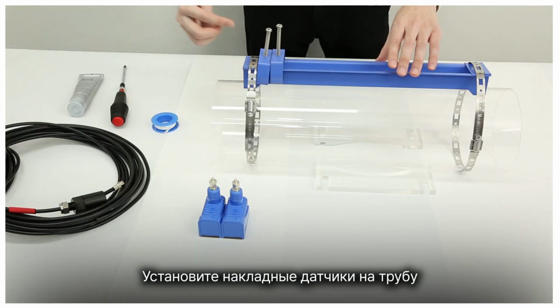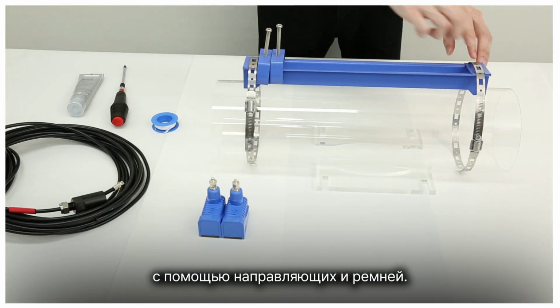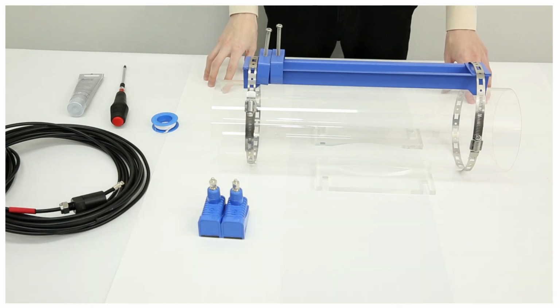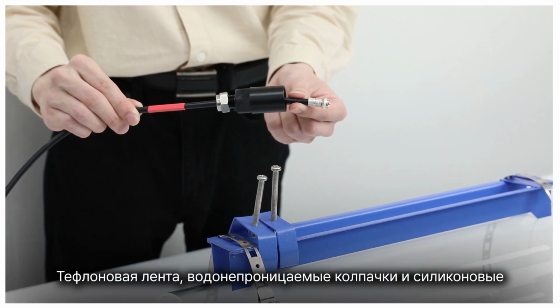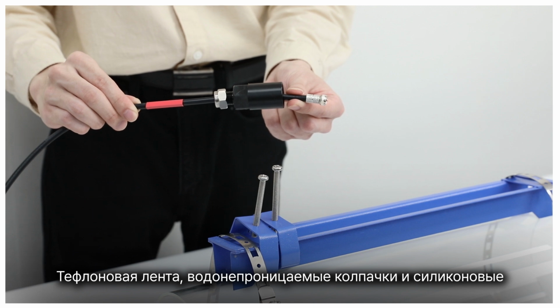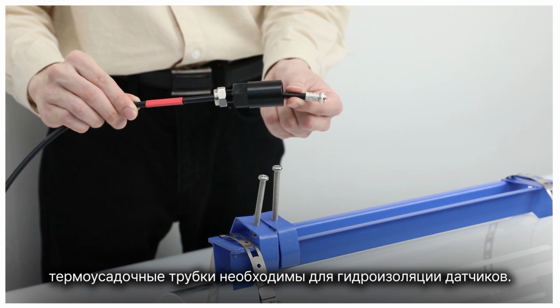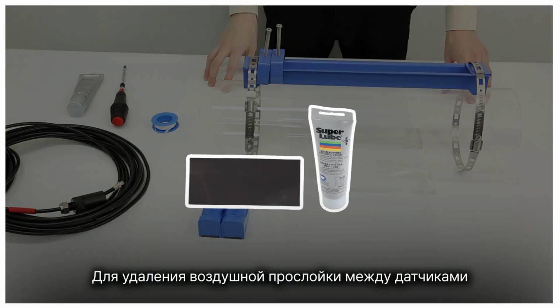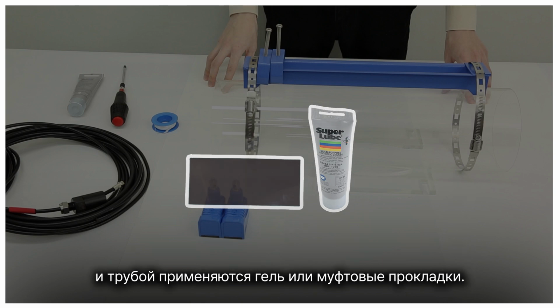Install the clamp-on transducers firmly on the pipe with the tracks and straps. The Teflon tape, waterproof caps, and silicone shrink tubes are required for waterproofing the transducers. Couplant is applied to remove the layer of air between the transducers and the pipe.